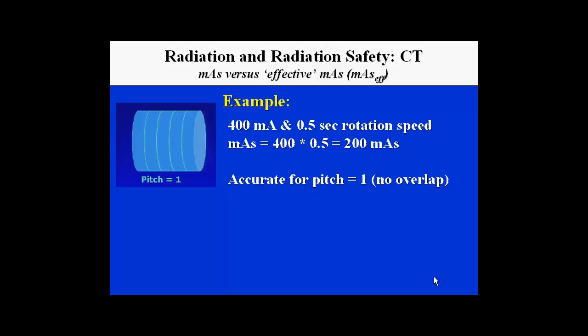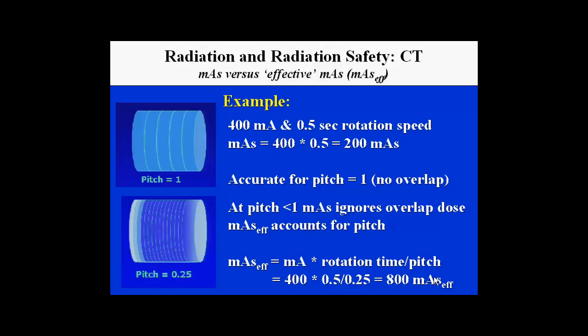For example, at a pitch of one — a direct overlap where the scanner Z-width per rotation equals table movement — with a 400 mA setting and 0.5 second rotation, the mAs is 200. However, at a pitch of less than one, as in cardiac CT, mAs ignores helical overlap. Therefore, mAs effective accounts for pitch: it equals mA times rotation time divided by pitch. At one-quarter pitch, the mAs effective becomes 800 — four times higher — significantly increasing radiation dose.